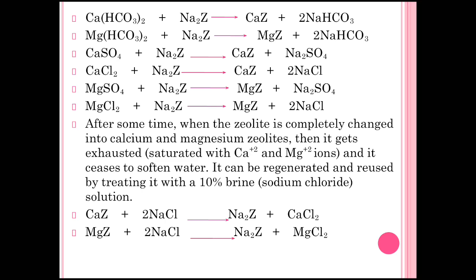The reactions: when calcium bicarbonate reacts with sodium zeolite, calcium zeolite is formed with removal of sodium bicarbonate. When magnesium bicarbonate is present in water, sodium zeolite reacts with magnesium bicarbonate forming magnesium zeolite with removal of sodium bicarbonate. All these reactions happen with sodium zeolite for impurities like CaSO₄, calcium dichloride, magnesium sulfate, and magnesium chloride — so both temporary and permanent hardness are removed.